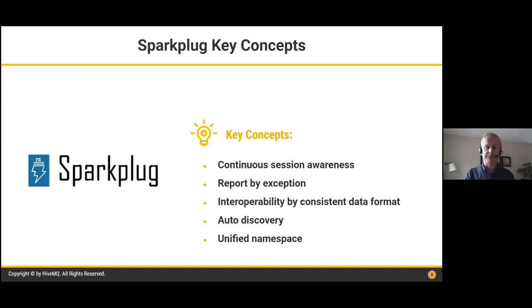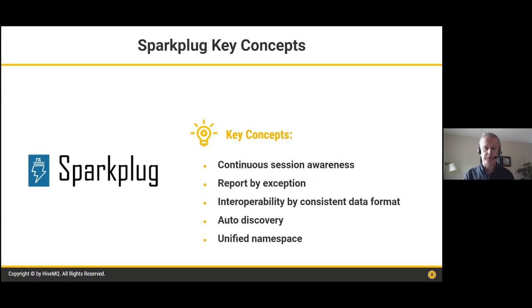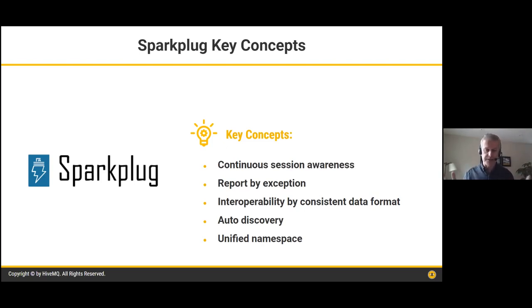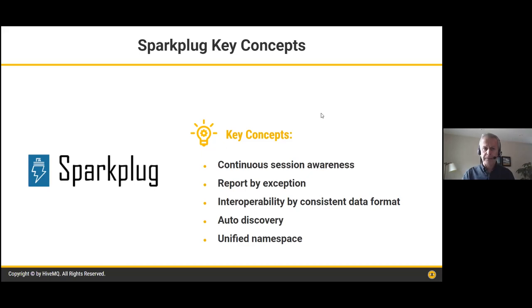The key concepts Spark Plug provides include: continuous session awareness, where clients are always present enabling bi-directional communication; report by exception, where instead of polling for tags you publish only when a tag value changes; interoperability with a consistent data format; auto-discovery, so when a new device is added to the system Spark Plug makes sure everyone knows it's there; and a unified namespace, meaning each participant in a Spark Plug system uses the same namespace, providing flexibility for integrating new components.